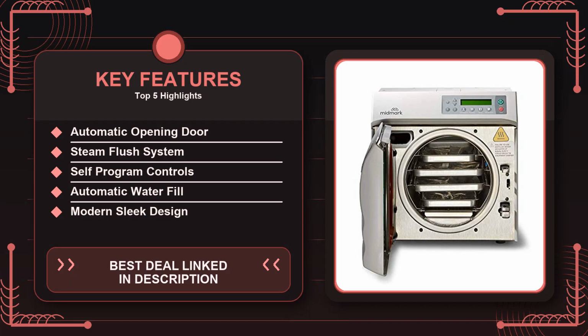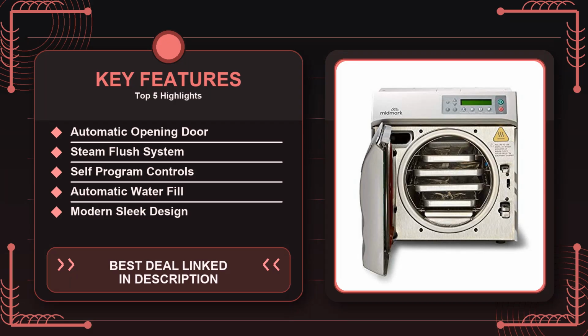The self-program controls let you set custom time-temperature combos, and the pre-programmed controls offer a few standard cycles: one for a quick 5-minute rinse, one for a full 121C sterilization, and another for a lower temperature dry heat option. This flexibility is handy if you're a dental hygienist who needs quick turnover of instruments, or a hobbyist who wants to sterilize 3D printed parts without overheating them. The downside is that there's no Wi-Fi or smartphone integration, so you can't get notifications on your phone when the cycle ends. You have to be in the room or keep checking the display.